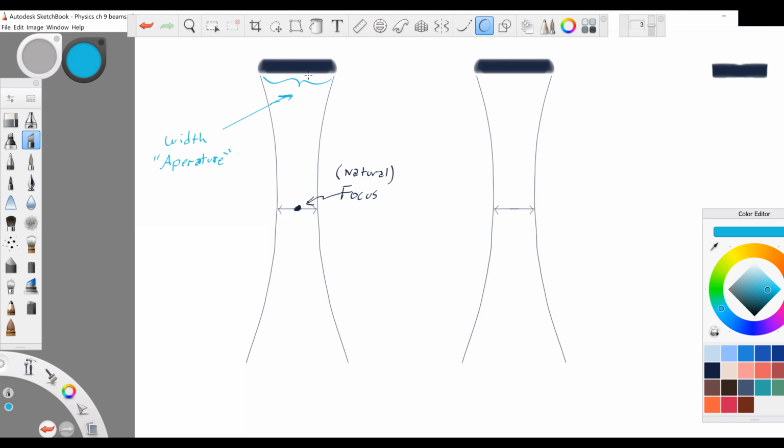So the sound beam is coming out of the entire width, right? That makes sense. At the focus, with a disc transducer, the width of the beam is 1/2 the aperture.